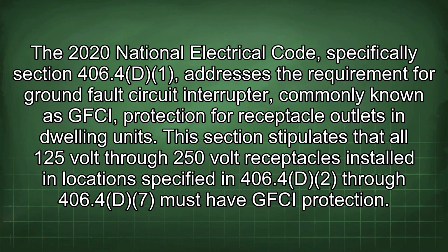The 2020 National Electrical Code, specifically Section 406.4(D), addresses the requirement for ground fault circuit interrupter, commonly known as GFCI, protection for receptacle outlets in dwelling units. This section stipulates that all 125 volt through 250 volt receptacles installed in locations specified in 406.4(D)(2) through 406.4(D)(7) must have GFCI protection.